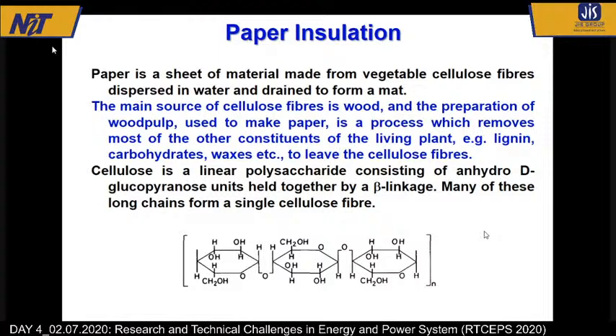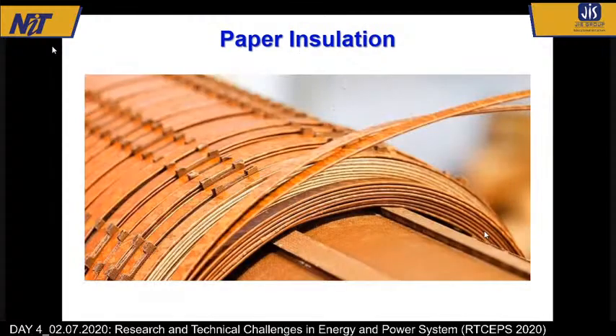But this paper degrades over time. This is a transformer winding where you can see the paper. Inside you have the copper or aluminum strip, which is covered by paper. This is called either single paper coating or double paper coating. And then you can see these small things called press board spacers, so that there is a small space between the individual discs. This is required for oil flow, otherwise there will be very poor cooling.